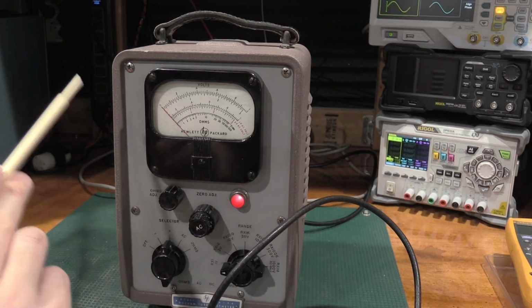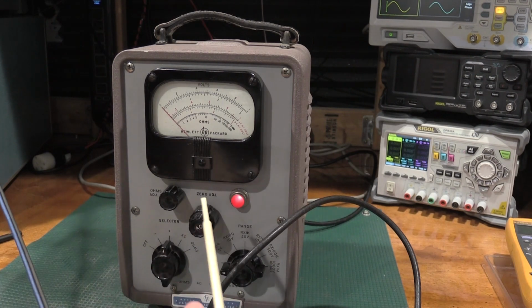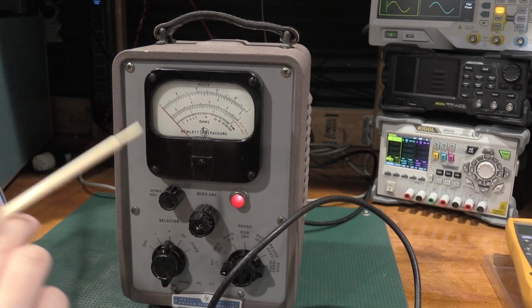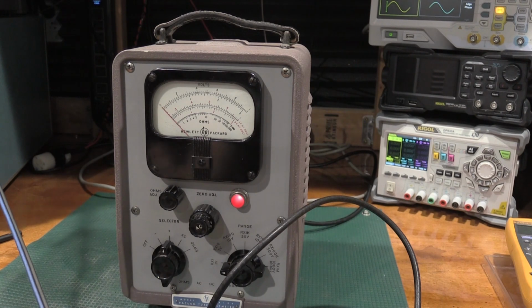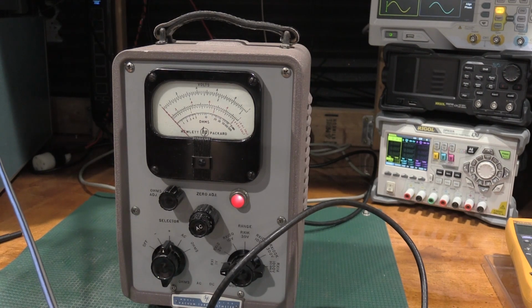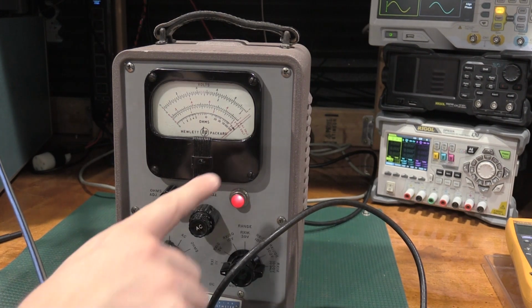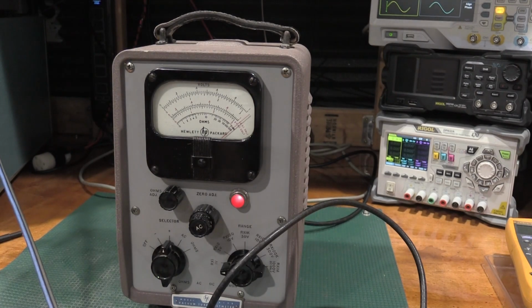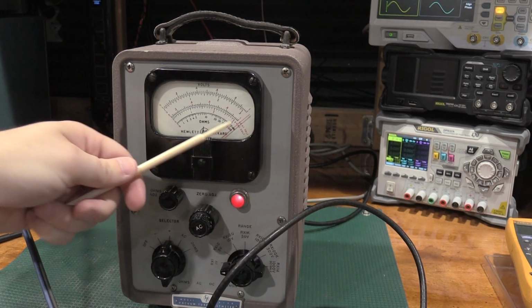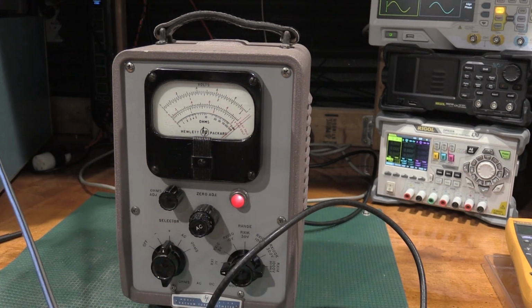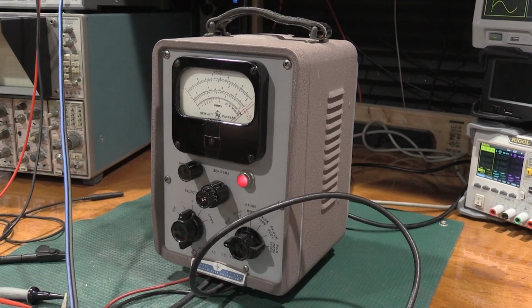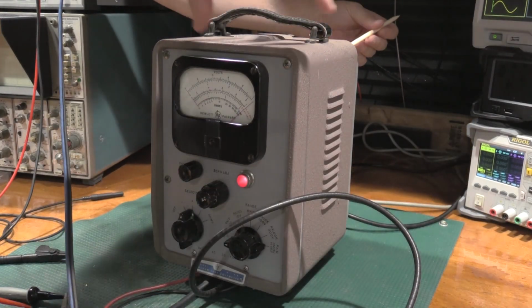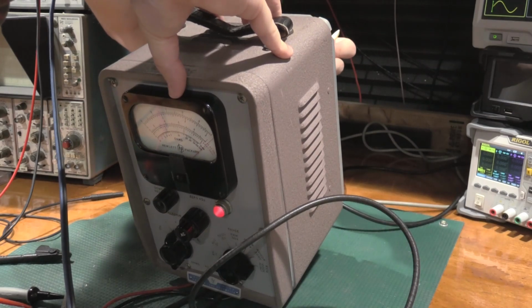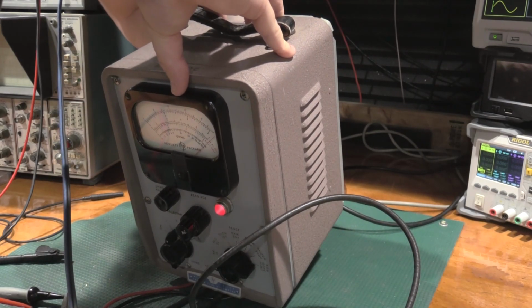So I put the very well balanced one in for the bridge, and put the amplifier tube in for the voltage amplifier, and now we're deflecting over. So I have enough deflection back. Now I need to dial it out and then check some of the ranges. So with you guys off to the side and me straight on, and the meter has done its appropriate warm-up.